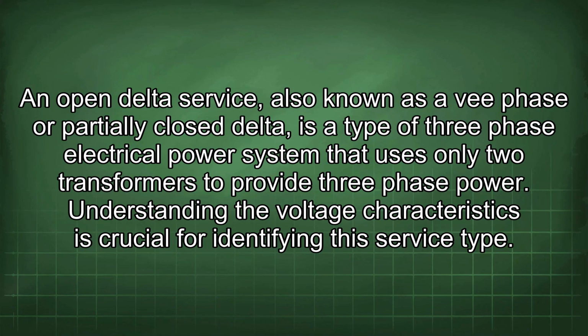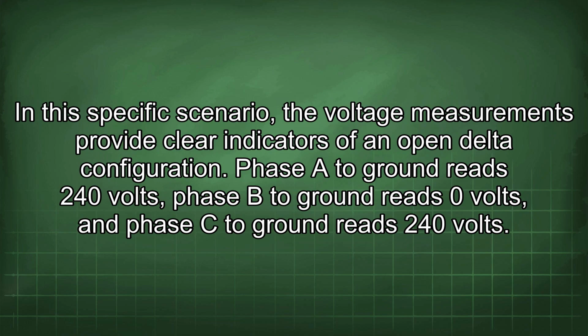An open delta service, also known as a V-phase or partially closed delta, is a type of three-phase electrical power system that uses only two transformers to provide three-phase power. Understanding the voltage characteristics is crucial for identifying the service type. In this specific scenario, the voltage measurements provide clear indicators of an open delta configuration.